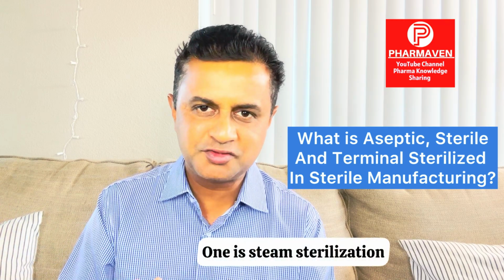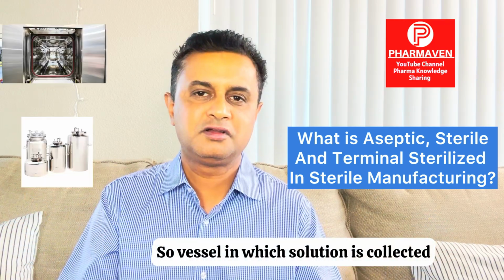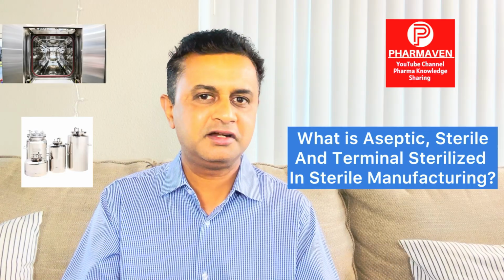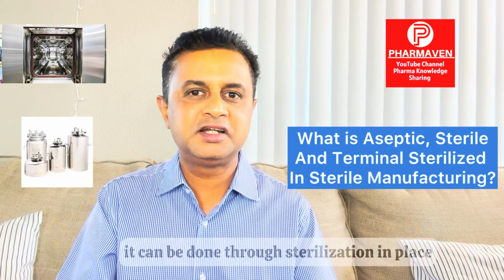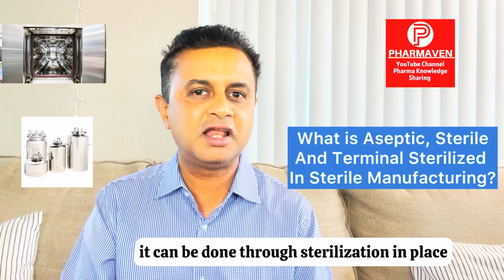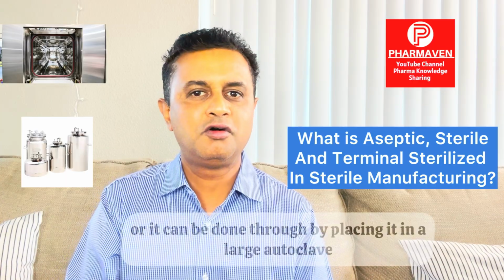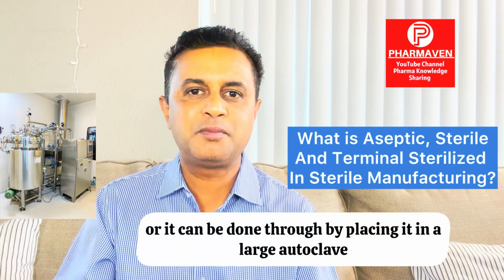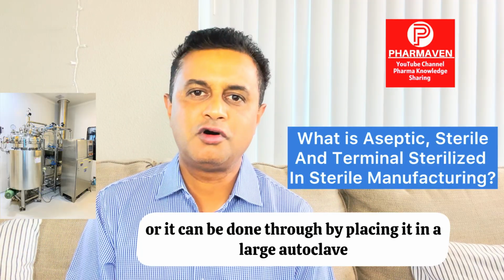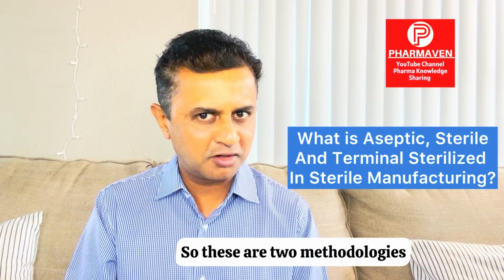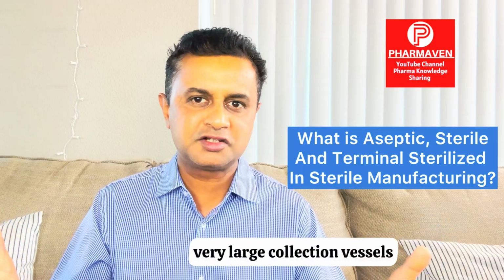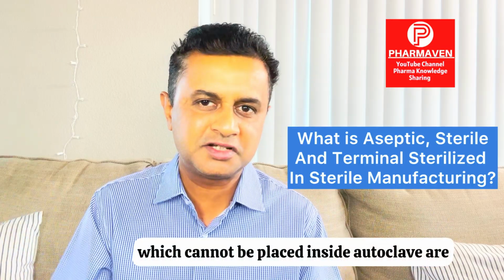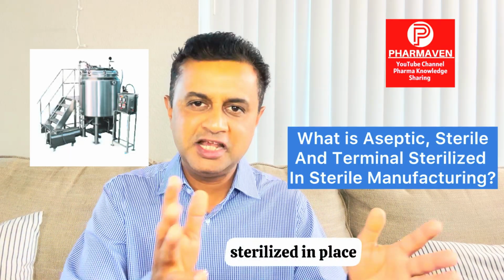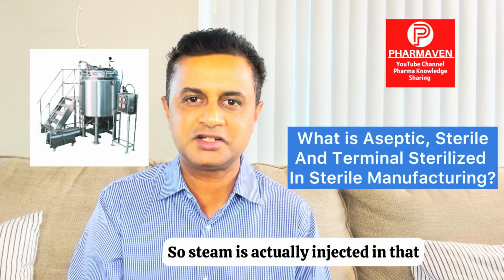One method is steam sterilization. The vessel in which the solution is collected can be steam sterilized, either through sterilization in place or by placing it in a large autoclave. These are the two methodologies. Very large collection vessels which cannot be placed inside an autoclave are sterilized in place, where steam is actually injected into them.